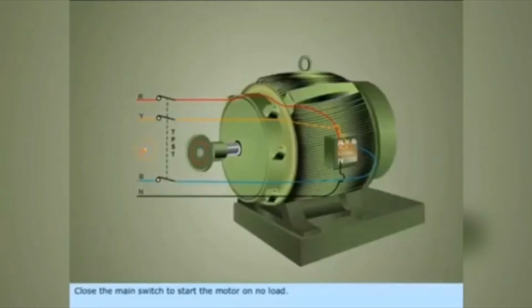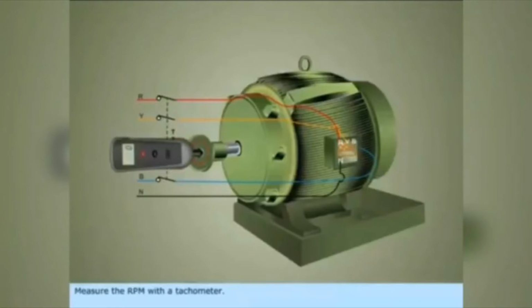Close the main switch to start the motor on no load. Observe the direction of rotation of the motor, say, looking from the left-hand side of the terminal box. You notice that the motor shaft is rotating in the clockwise direction. Measure the RPM with a tachometer. Open the switch.